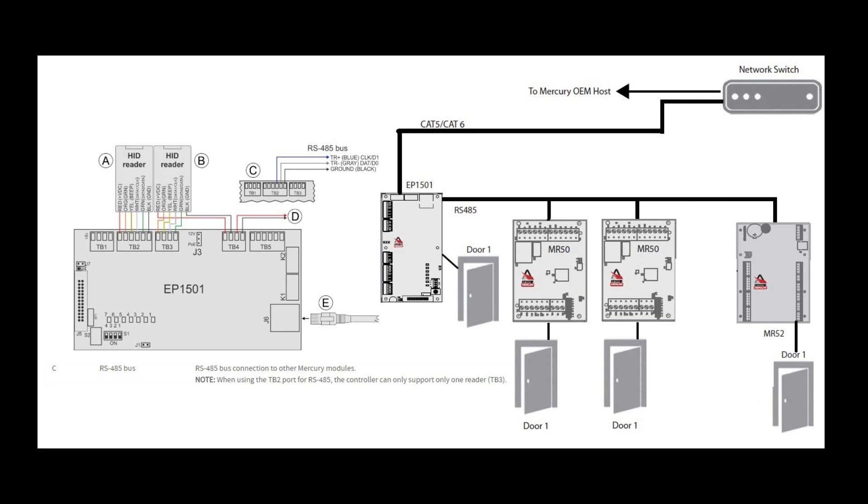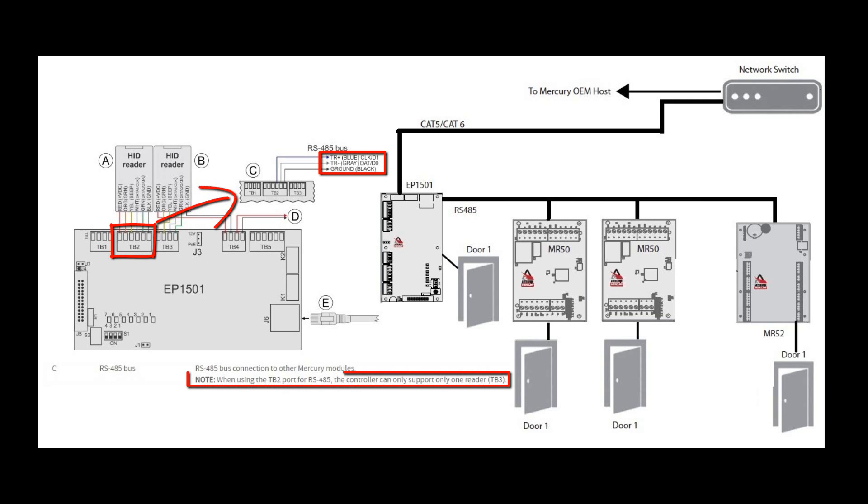When using an EP1501 there is a slight difference. When downstreaming sub-panels from an EP1501, since there is no RS485 on the EP1501, you have to use the reader TB2 port where the clock becomes TR+, the data becomes TR-, and ground is the ground. When you do this, the EP1501 can only support one reader.